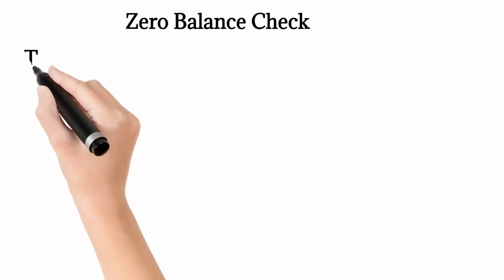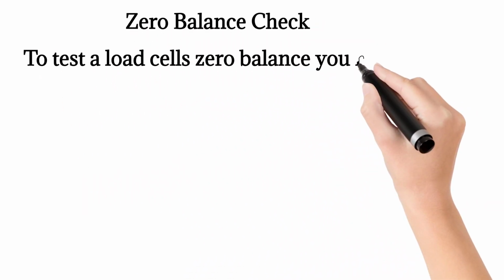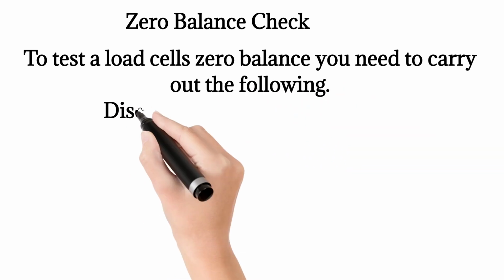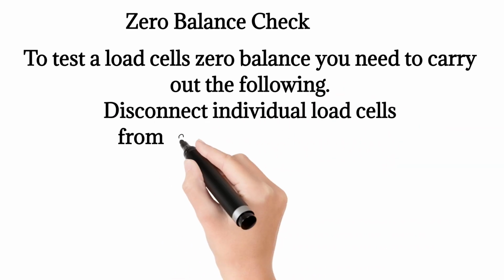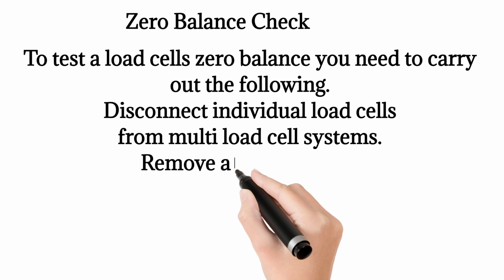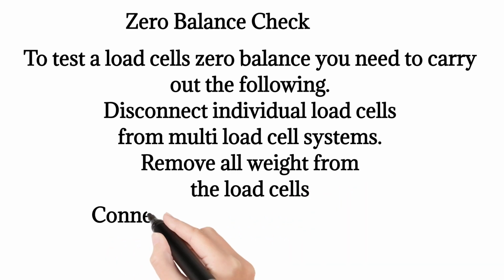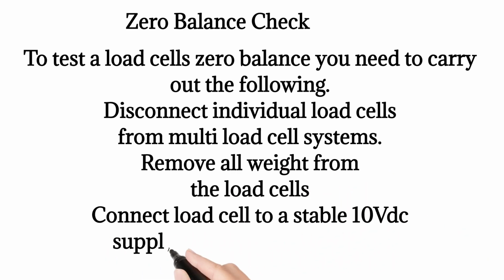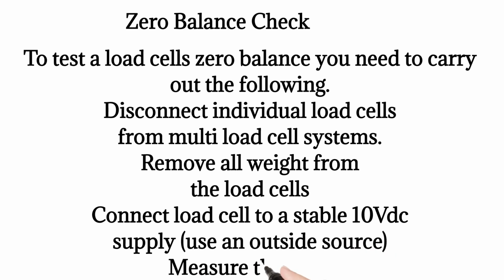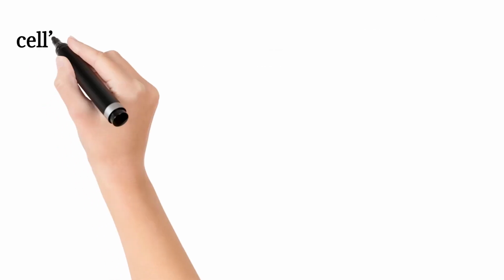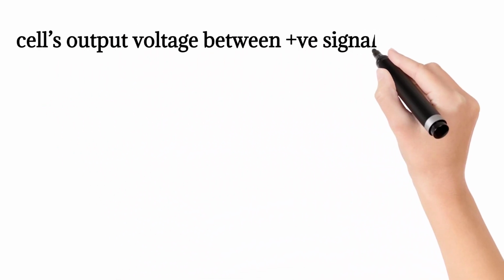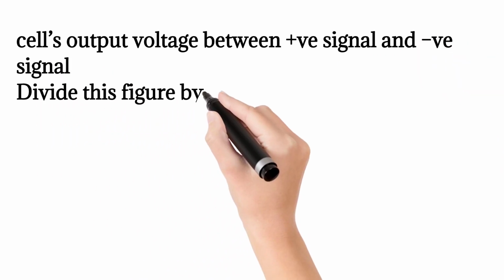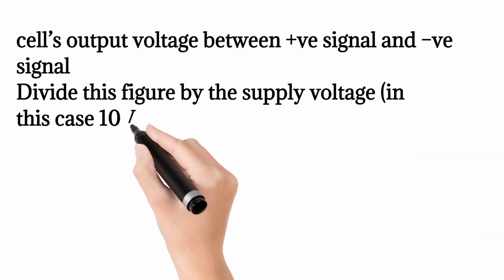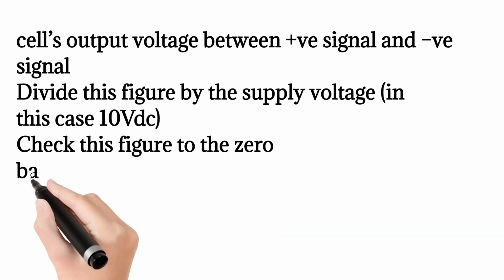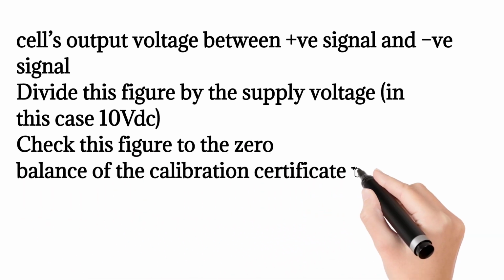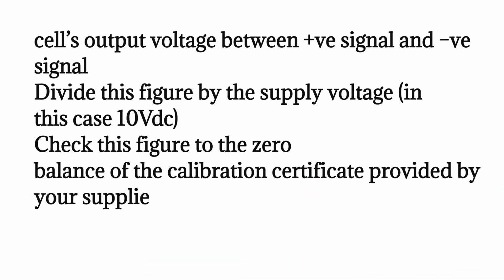Zero balance checks. To test a load cell's zero balance, you need to carry out the following. Disconnect individual load cells from multi-load cell systems. Remove all weight from the load cells. Connect the load cell to a stable 10V DC supply. Use an outside source. Measure the load cell's output voltage between plus V signal and minus V signal. Divide this figure by the supply voltage, in this case 10V DC. Compare this figure to the zero balance on the calibration certificate provided by your supplier.